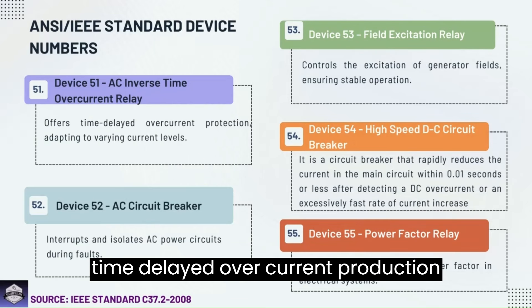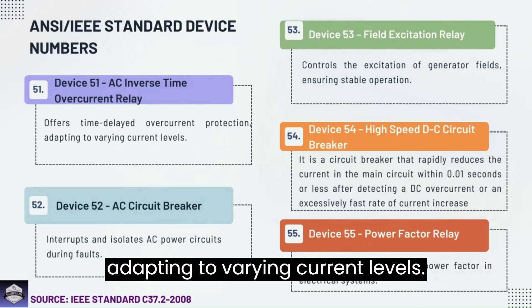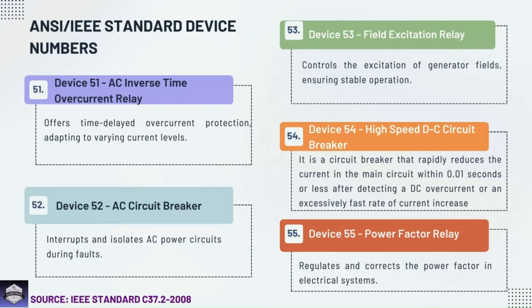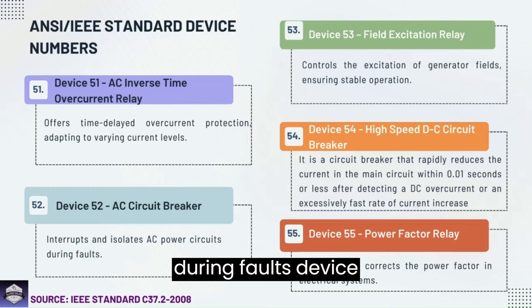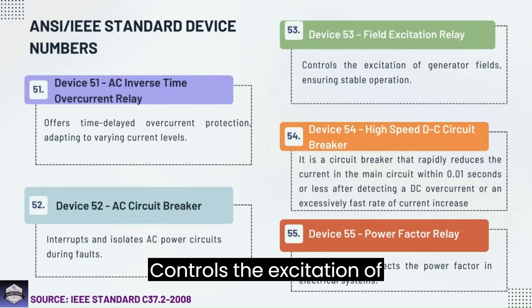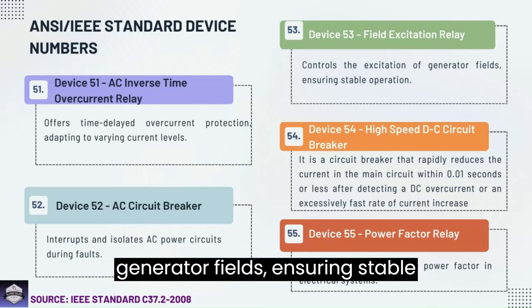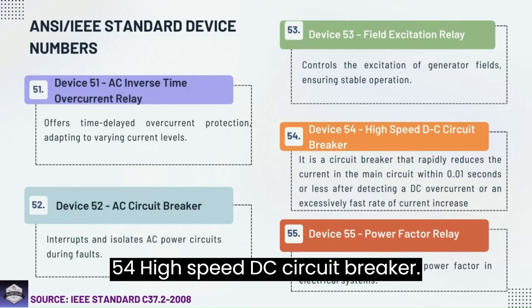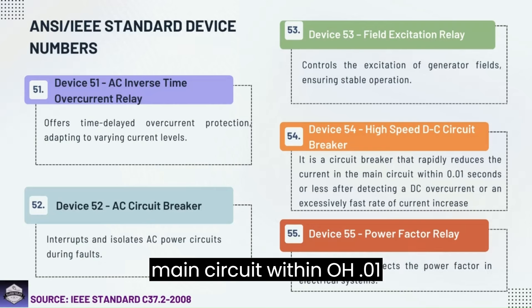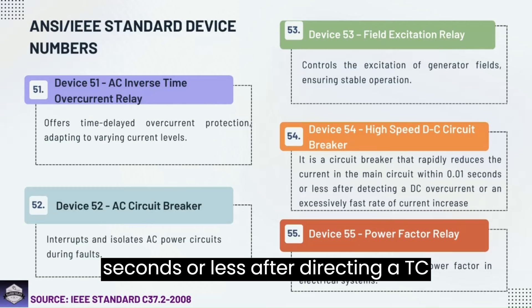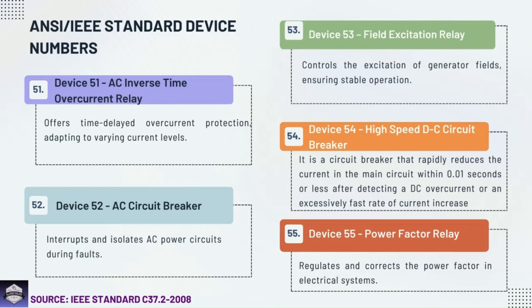Device 52: AC circuit breaker — interrupts and isolates AC power circuits during faults. Device 53: Field excitation relay — controls the excitation of generator fields, ensuring stable operation. Device 54: High speed DC circuit breaker — a circuit breaker that rapidly reduces the current in the main circuit within 0.01 seconds or less after detecting a DC overcurrent or excessively fast rate of current increase.